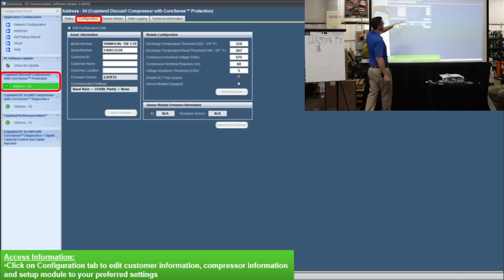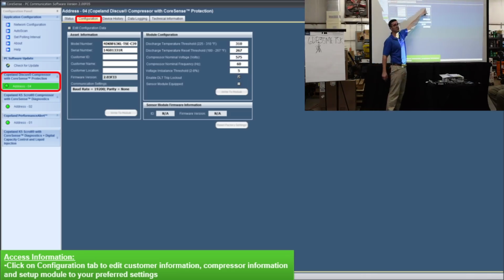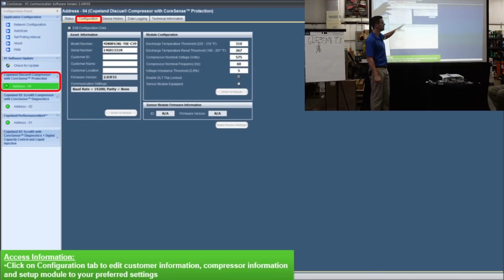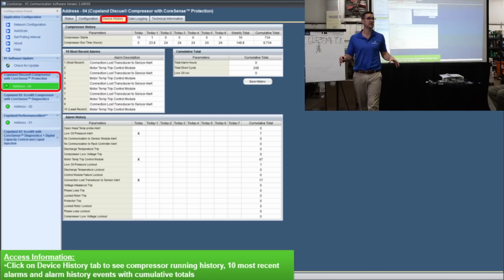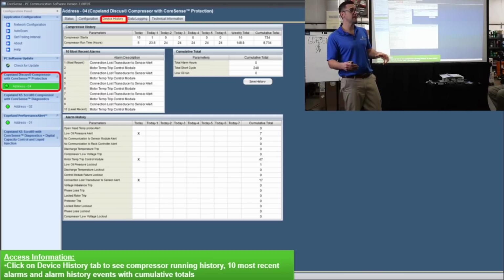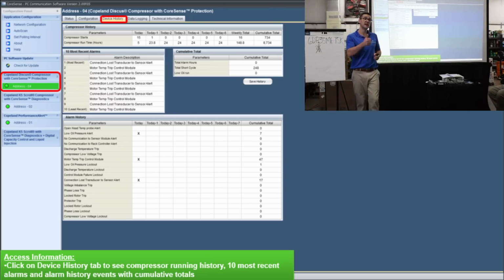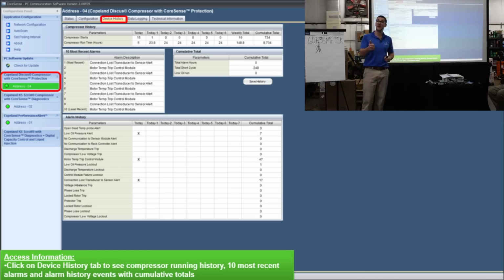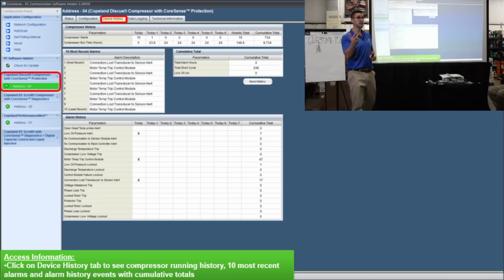Excellent. Then you can change some settings. If you don't want it to trip out at 310, you can get it at, say, 270 inside that head and protect that compressor a little bit earlier. As well as voltage imbalance if you want. But here's where all the cool information is. As a mechanic, if you can go out and see how long that compressor's been running, how many times it started that day and how many times it stopped, if it tripped, right? This is such great information.